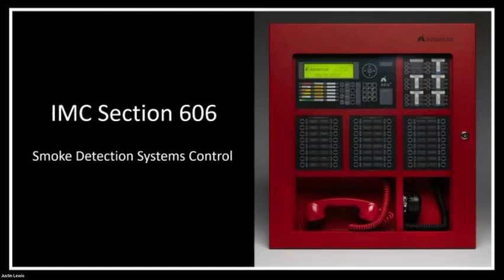We often see systems specified at 2,000 CFM design with a plus or minus 5% specification. The units are typically direct drive units with an external static pressure listed at 0.5. Issues arise when systems operate at a lower static loss than expected. The unit delivers 2,030 CFM on low speed because we have an open plenum return and oversized ductwork to accommodate for sound. Now that system requires a duct detector, and we're in the 11th hour. We've seen duct detectors added to units late in the game and cause delays in turnover. These are potential issues we can help identify before the schedule is impacted.